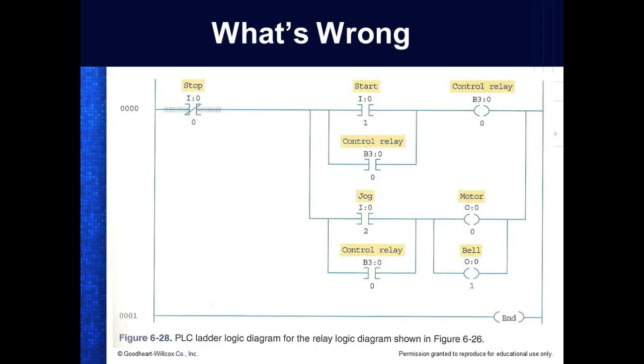So this is an internal, we call this an internal relay. This is software. There's no hardware at all about it. It's a B3. It's not an output. Once it is energized by the start button, this has to be true. And then when this becomes true, this would energize, which affects the other two that have the same address, correct? Right. We close this one, so now I can let go of my start button and it seals in. We call this a memory circuit.